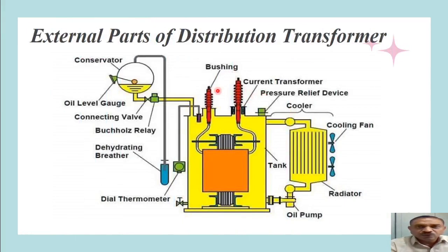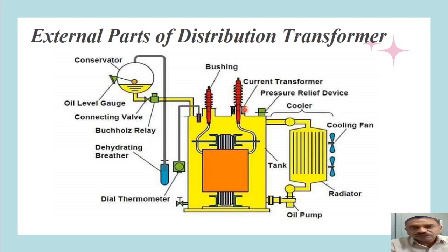Now let us see all the external parts of a distribution transformer. Whatever parts we described earlier are contained in a box — the whole transformer is mounted inside a tank filled with oil, represented by yellow color. At the top, the tank is provided with bushings, through which we connect the primary and secondary windings. Depending upon voltage level, the size and height of the bushings will vary. A current transformer is fitted near the bushings, which takes care of measurement and protection. It steps down the current of primary or secondary windings to a level accepted for measurement and protection.